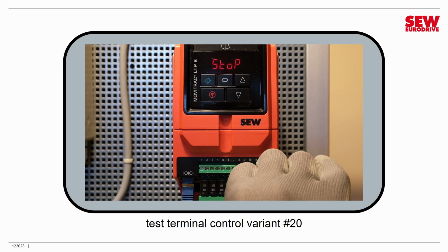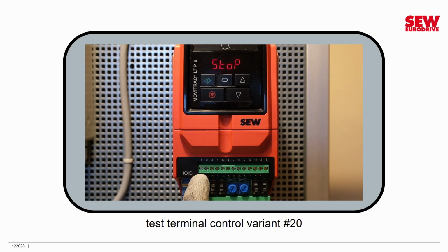and we're going to play with those 2 stop ramps. So what I'm going to do is accelerate all the way up to 1800 RPM, and we're going to do a normal stop first. So I'll turn digital input 1 off. And you can see that definitely took a few seconds. And now I'm going to go back to my maximum speed again. And I'm going to turn digital input 1 and digital input 2 on at the same time, which triggers a fast ramp. And you can see it did stop a lot quicker.